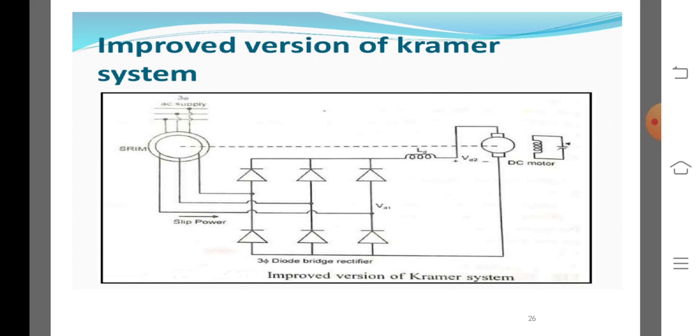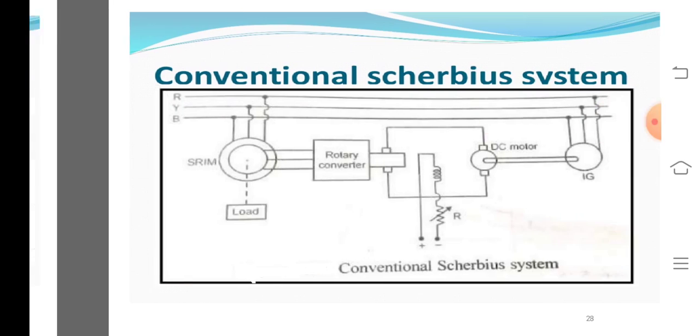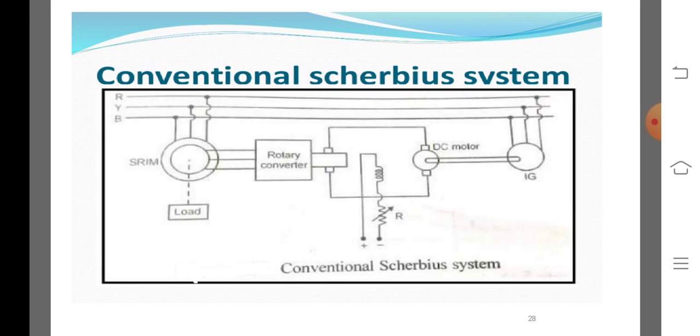The rotary converter has a fixed ratio between the AC side and DC voltage side, so the voltage on its AC side also changes. This AC voltage is given to the slip rings of main motor A. So, the voltage injected in the rotor of the main motor changes, which produces the required speed control.